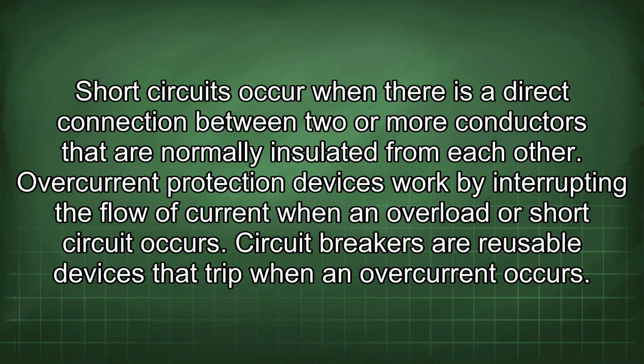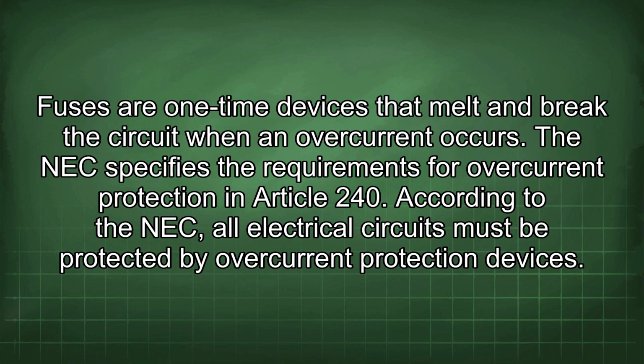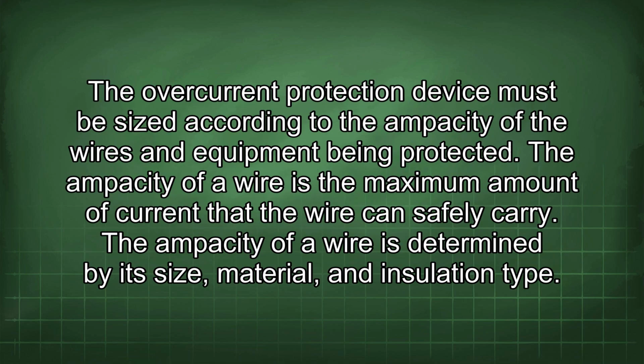Circuit breakers are reusable devices that trip when an overcurrent occurs. Fuses are one-time devices that melt and break the circuit when an overcurrent occurs. The NEC specifies the requirements for overcurrent protection in Article 240. According to the NEC, all electrical circuits must be protected by overcurrent protection devices. The overcurrent protection device must be sized according to the ampacity of the wires and equipment being protected. The ampacity of a wire is the maximum amount of current that the wire can safely carry. The ampacity of a wire is determined by its size, material, and insulation type.